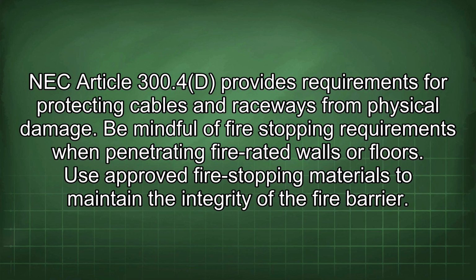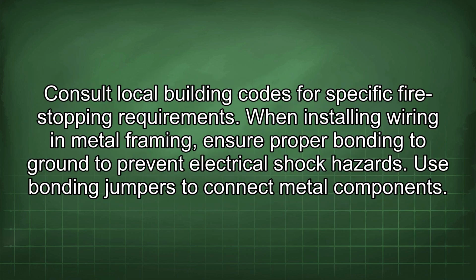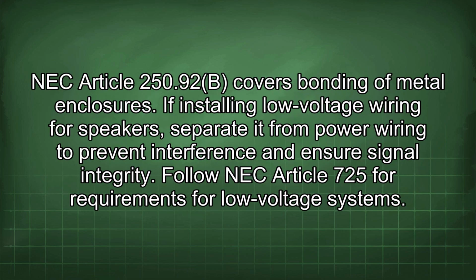Be mindful of fire-stopping requirements when penetrating fire-rated walls or floors. Use approved fire-stopping materials to maintain the integrity of the fire barrier. Consult local building codes for specific fire-stopping requirements. When installing wiring in metal framing, ensure proper bonding to ground to prevent electrical shock hazards. Use bonding jumpers to connect metal components. NEC Article 250.92(B) covers bonding of metal enclosures.